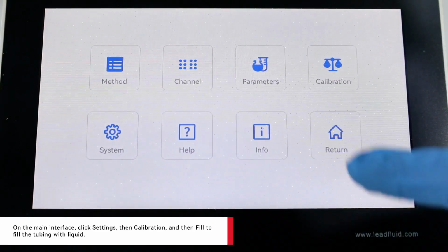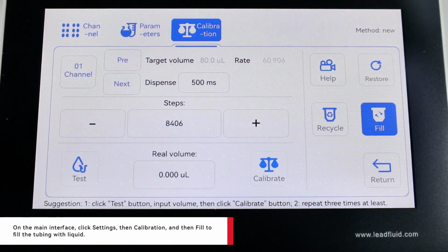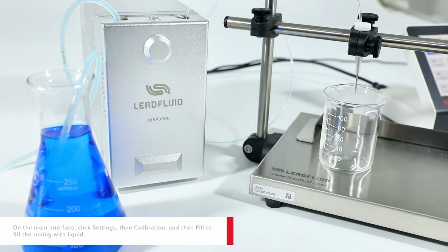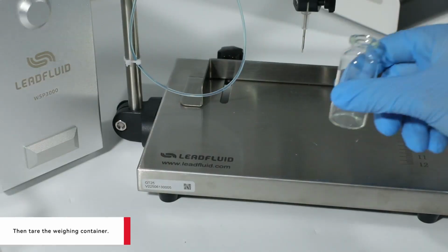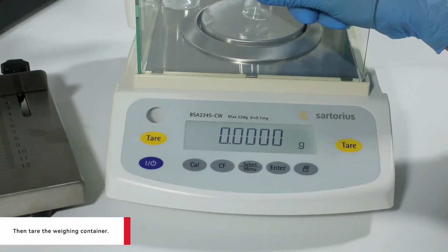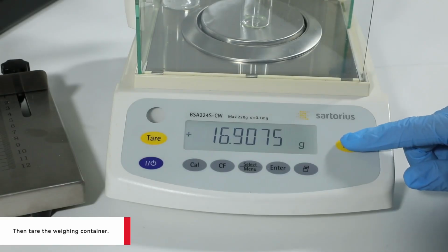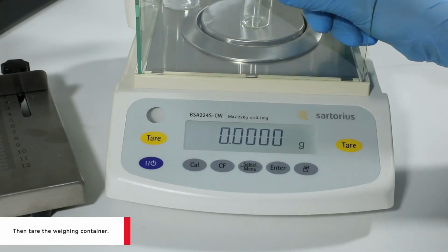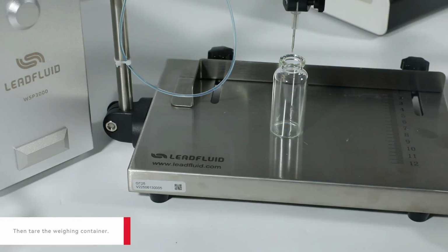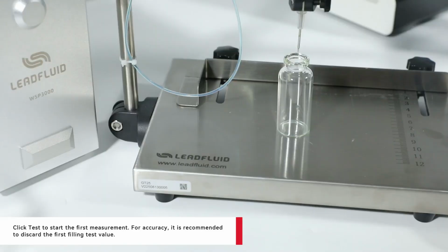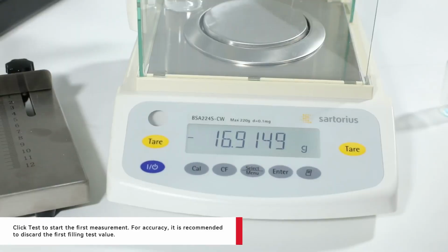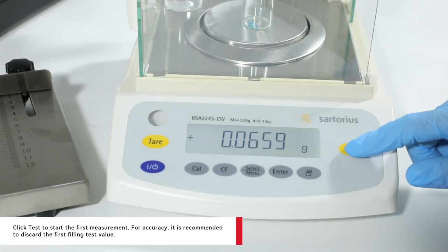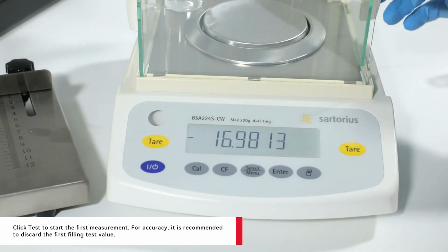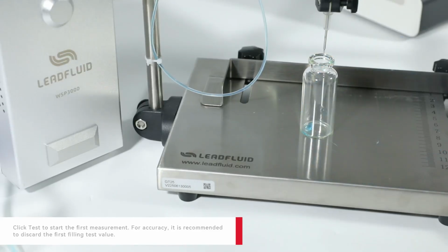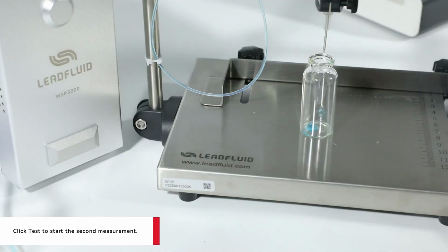On the main interface, click Settings, then Calibration, and then fill the tubing with liquid. Then tare the weighing container. Click Test to start the first measurement. For accuracy, it is recommended to discard the first filling test value. Click Test to start the second measurement.